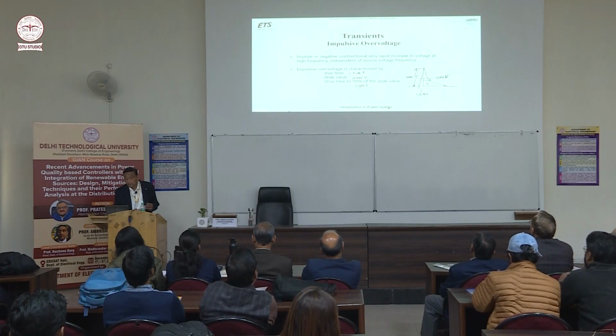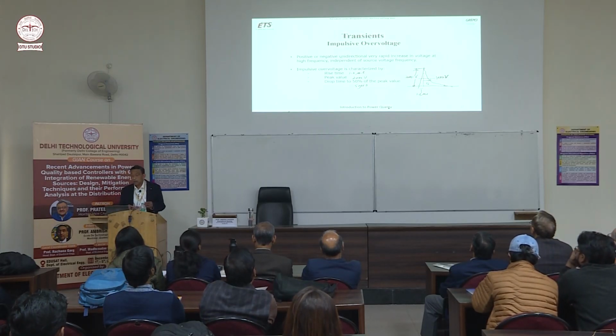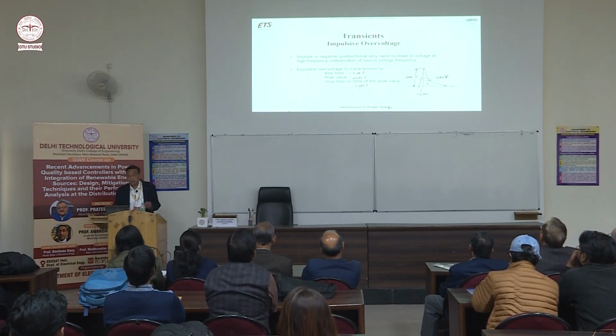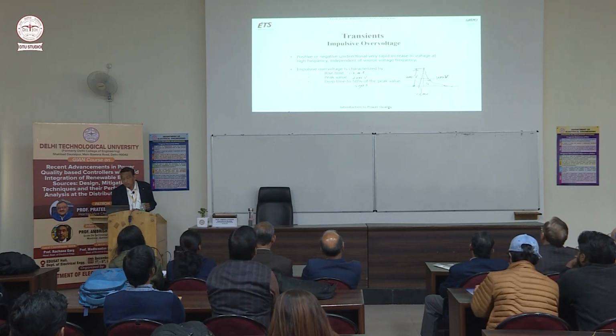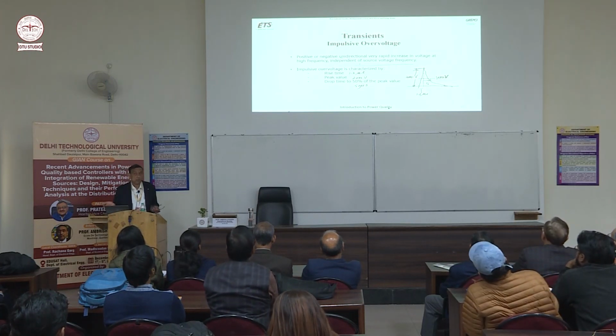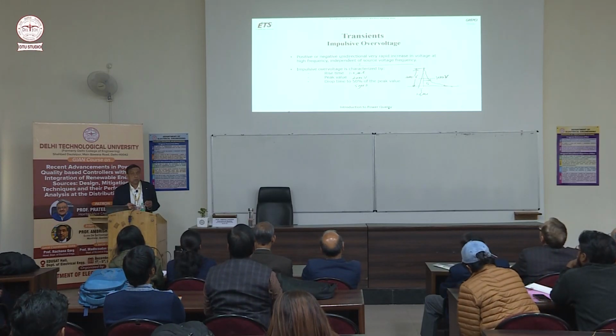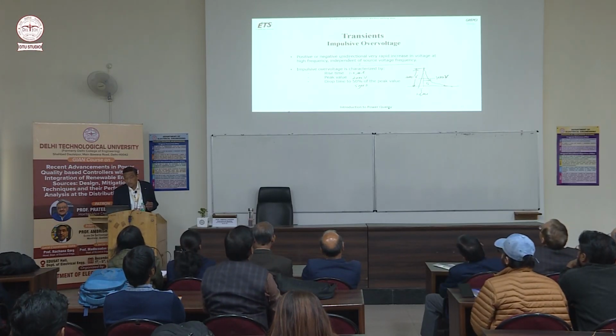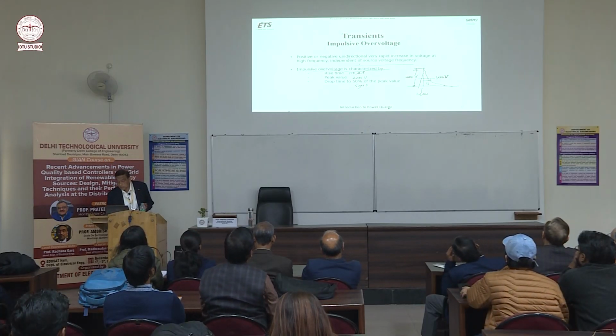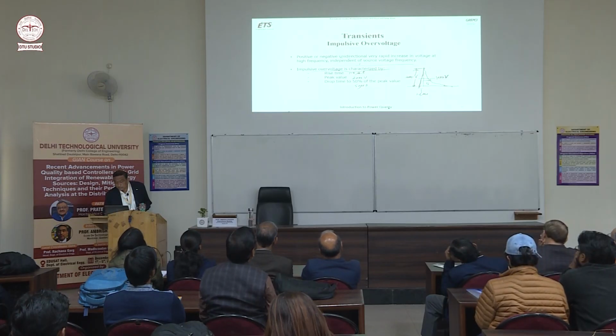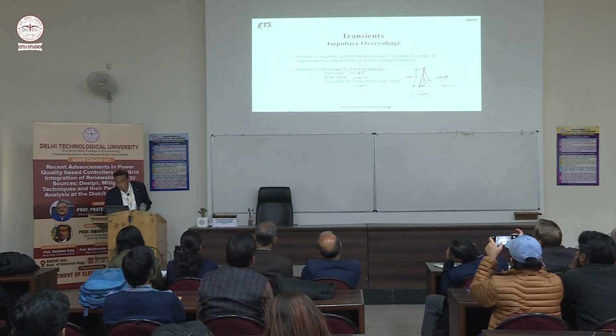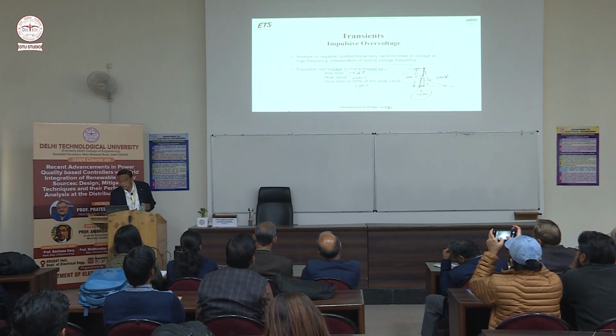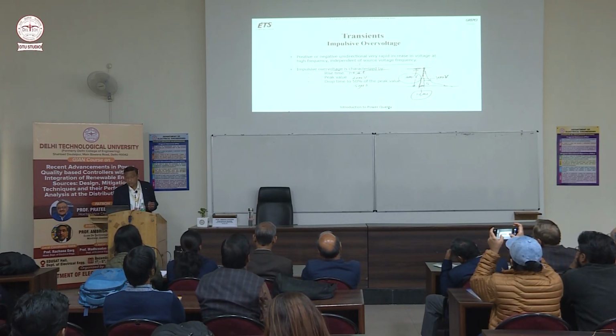Positive or negative, unidirectional, very rapid increase in voltage at high frequency, independent of source voltage frequency. Suppose you have 50 Hz or 60 Hz, but it has nothing to do with this. It is in microsecond, high frequency. Impulsive over voltage is characterized by rise time. So you see, this is an example, impulsive voltage. So rise time is this, 1.2 microsecond. Peak value, for example, it is just an example, okay, 2000 volt in 1.2 microsecond.